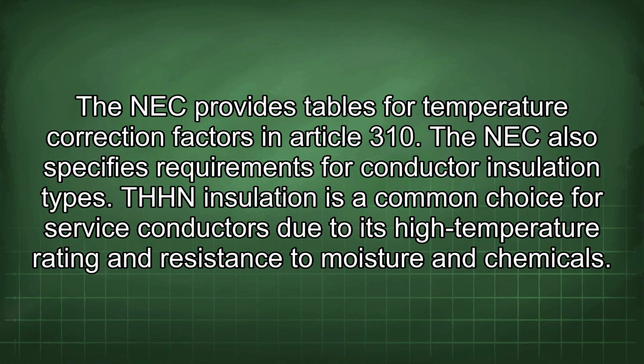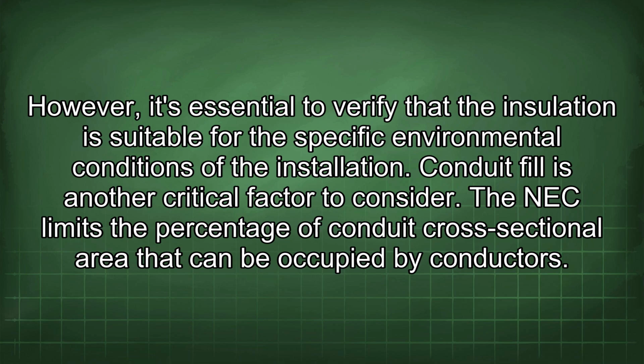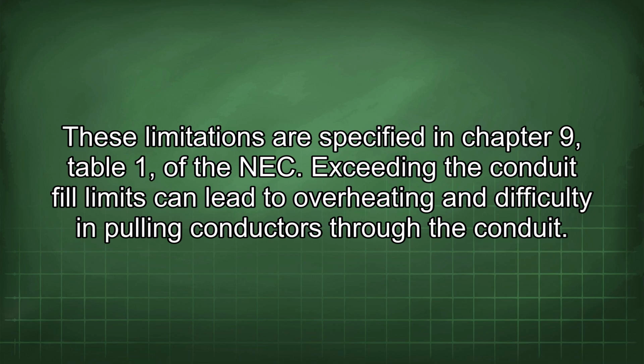The NEC also specifies requirements for conductor insulation types. THHN insulation is a common choice for service conductors due to its high temperature rating and resistance to moisture and chemicals. However, it's essential to verify that the insulation is suitable for the specific environmental conditions of the installation. Conduit fill is another critical factor to consider. The NEC limits the percentage of conduit cross-sectional area that can be occupied by conductors. These limitations are specified in Chapter 9, Table 1 of the NEC. Exceeding the conduit fill limits can lead to overheating and difficulty in pulling conductors through the conduit.